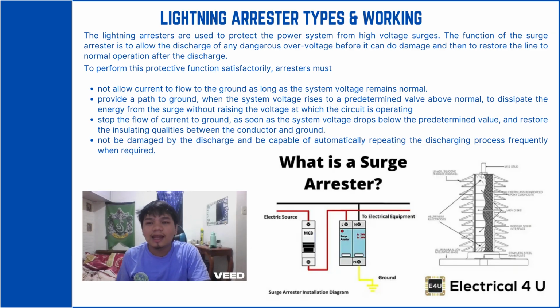So as you can see, a lightning arrestor is used to protect the power systems from high voltage surges, such as those caused by lightning or sudden changes in voltage. Its main function is to discharge an excessive voltage safely to the ground before it can damage the equipment and then restore the system to normal operation afterward.